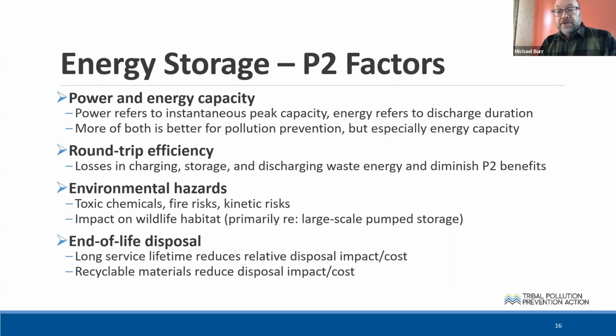So then the other factor is round trip efficiency. Different energy storage systems have different levels of efficiency, and also within a battery type, depending on how it's designed and managed, even a given lithium battery can have a wide range of efficiencies. Generally, lithium batteries are pretty efficient, considered about 90% in that neighborhood. We'll get into it when we show the next slide, there's a table comparing things. But there's a wide range, some energy storage systems are more like 40 or 50% efficient.